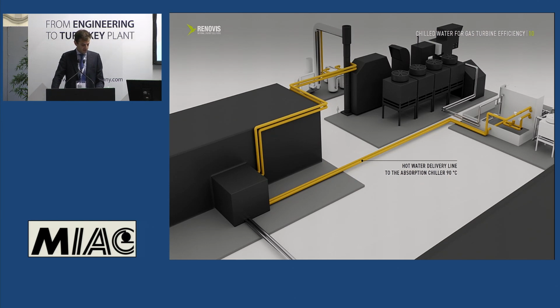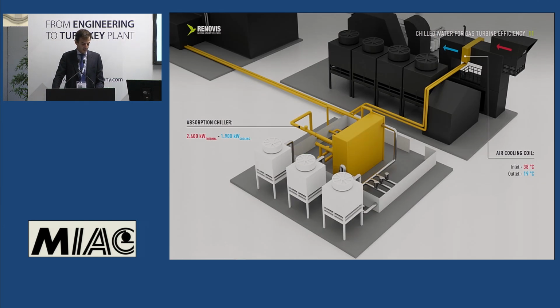The absorption chiller, based on lithium bromide technology, generates a cooling capacity of 1,900 cooling kilowatts. The chilled water produced by it at a temperature of 7 Celsius degrees is then pumped to the specially designed cooling coil installed in the intake chamber to drastically cool down the air entering the gas turbine. We are able to subtract almost 20 Celsius degrees from the air entering the gas turbine, bringing the gas turbine operating conditions back to nominal. That is more or less 33% of efficiency in energy production.